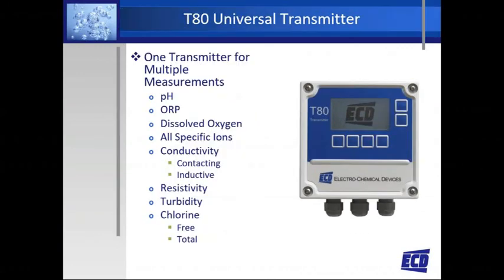One transmitter for multiple process measurements. So you can do any of the measurements from pH, ORP, dissolved oxygen, any of the selective ions, conductivity, resistivity, turbidity, and chlorine, all with the same instrument. Whatever sensor you attach to this transmitter, that's what it becomes. No hardware or software changes between the different measurements.